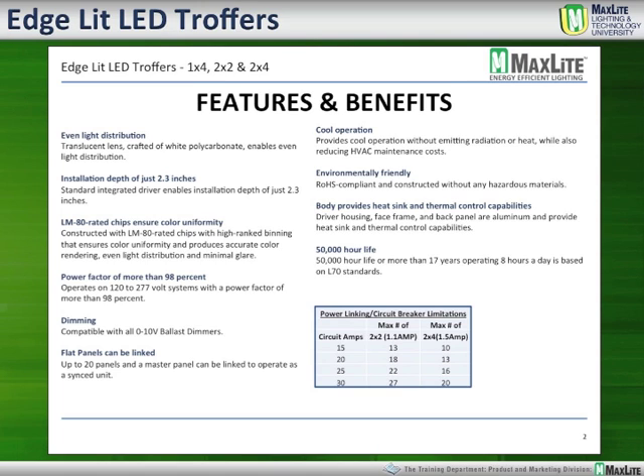These products run cool. They're over-designed when it comes to the thermodynamics. As mentioned earlier, the temperature has a huge impact on the life of LED products. Most are running their assumed temperatures at 25°C, and when you are operating these fixtures below that temperature, generally it extends the life of the fixture. Generally it slows down the lumen depreciation.